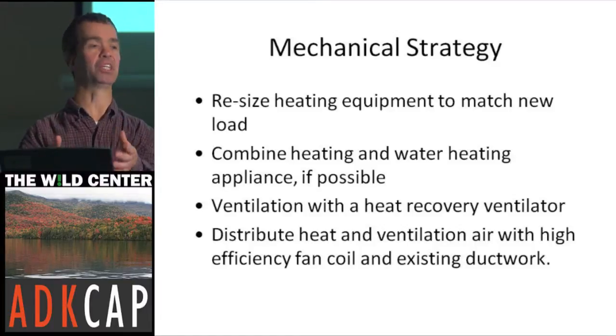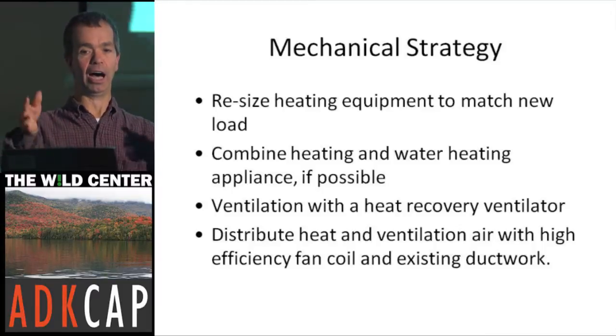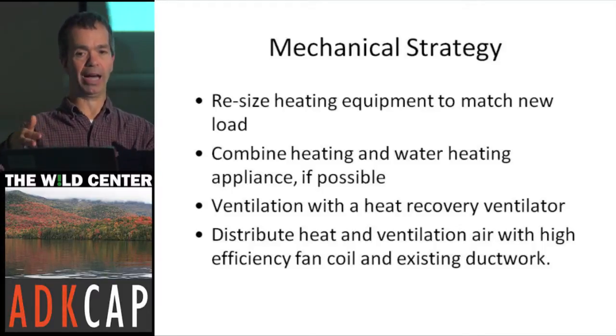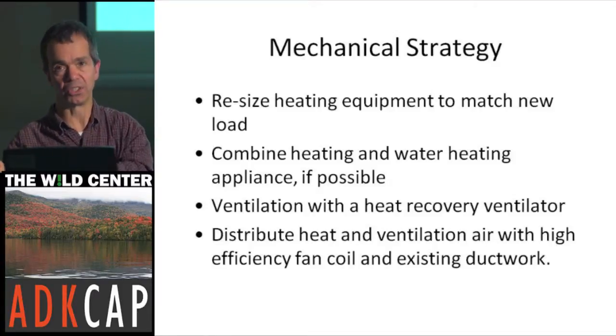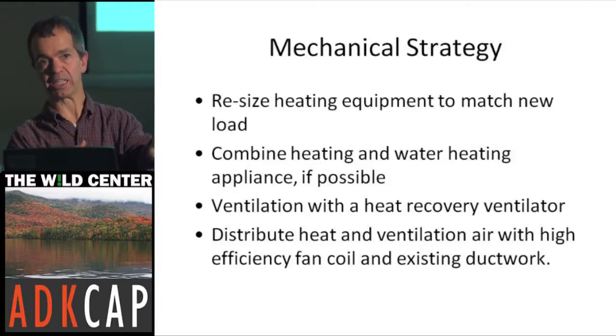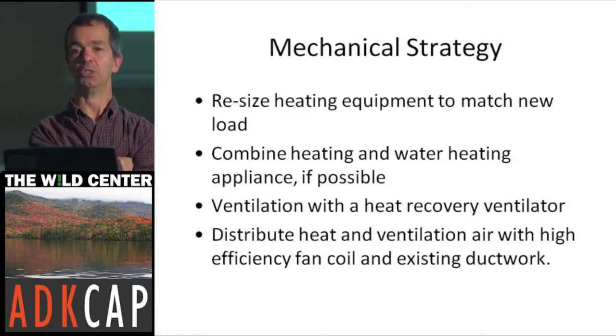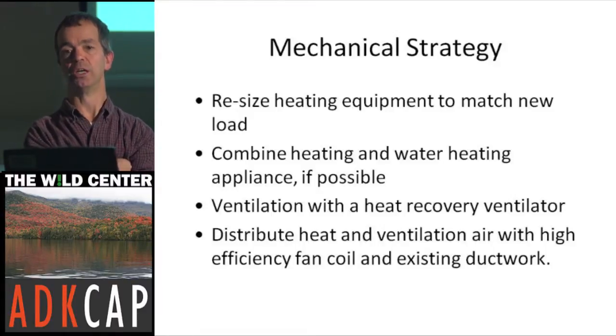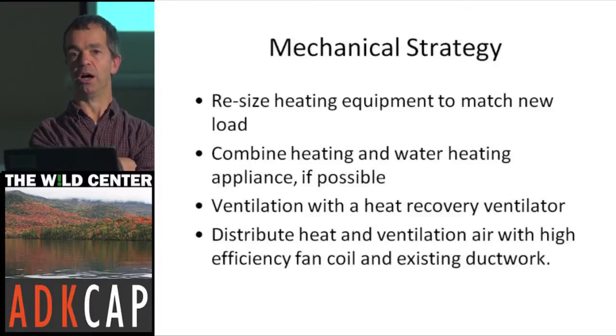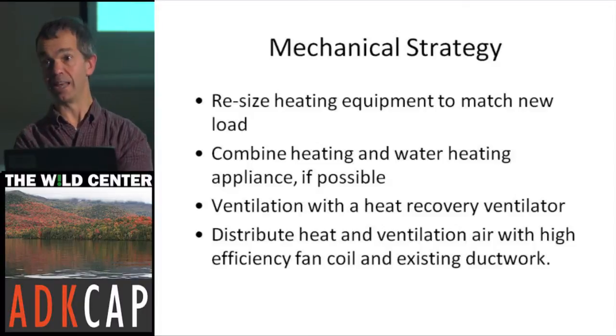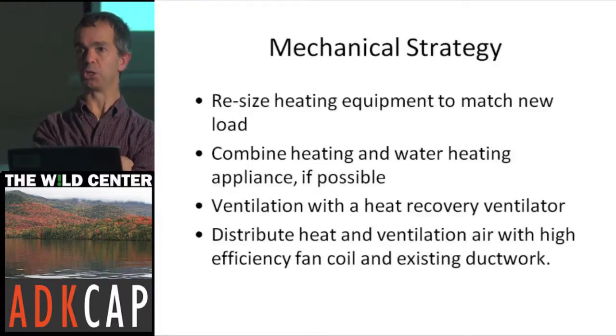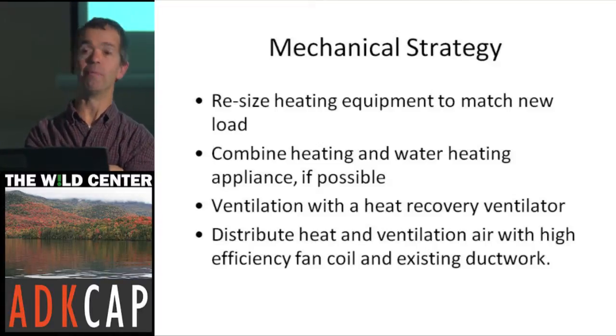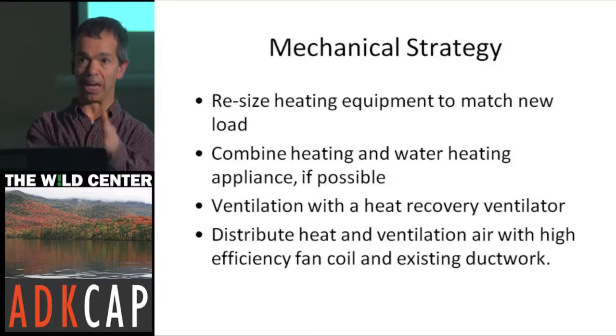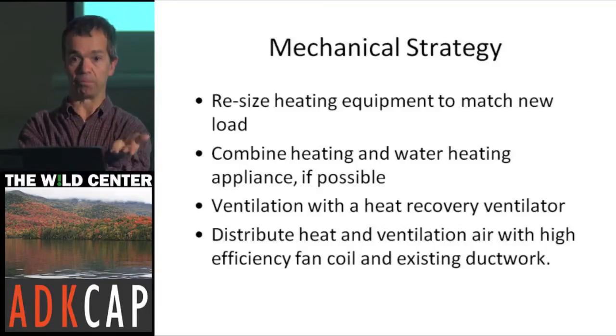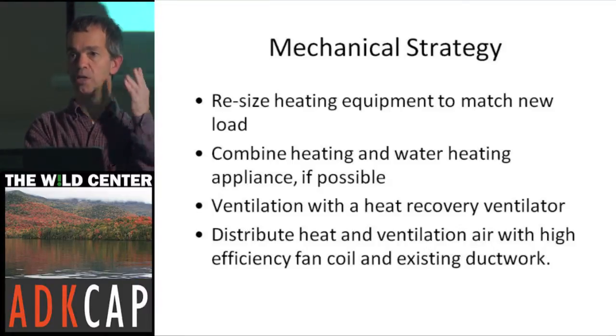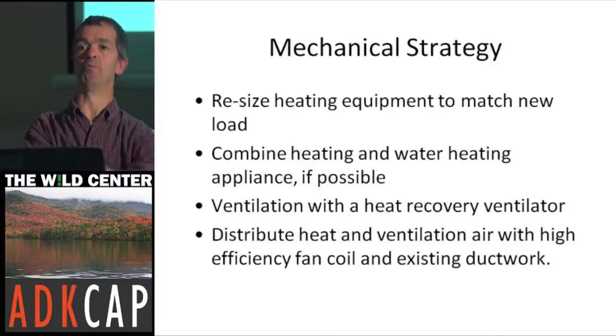This is where we have a big disconnect in general in our country. Equipment systems are sold on size and request, and housing envelopes don't typically meet anything of what we set these bogeys at. So to be safe, mechanical contractors put in systems that will deliver the most amount of heat on a design day, a day like the one day of the year that it's 22 below zero and the wind is blowing at 40 miles an hour.